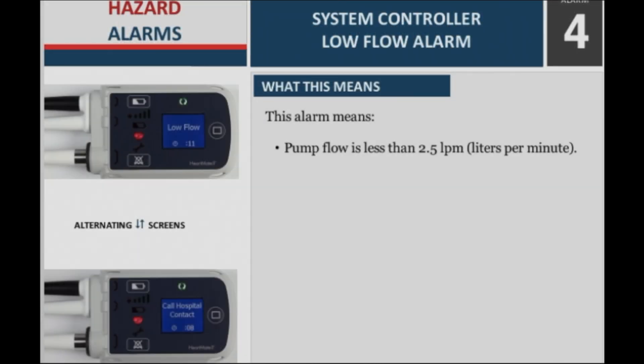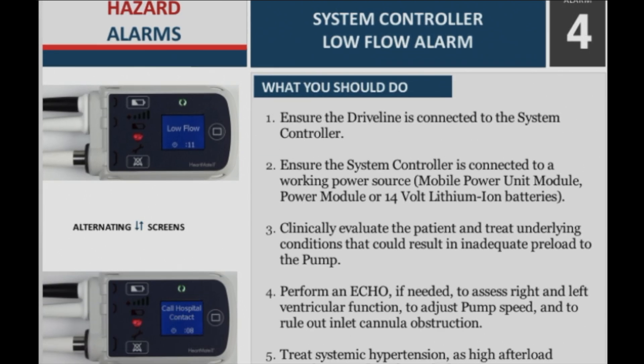What this means: Pump flow is less than 2.5 liters per minute. What you should do: Step 1 — Ensure the driveline is connected to the system controller. Step 2 — Ensure the system controller is connected to a working power source: mobile power unit module, power module, or 14V lithium ion batteries. Step 3 — Clinically evaluate the patient and treat underlying conditions that could result in inadequate preload to the pump.